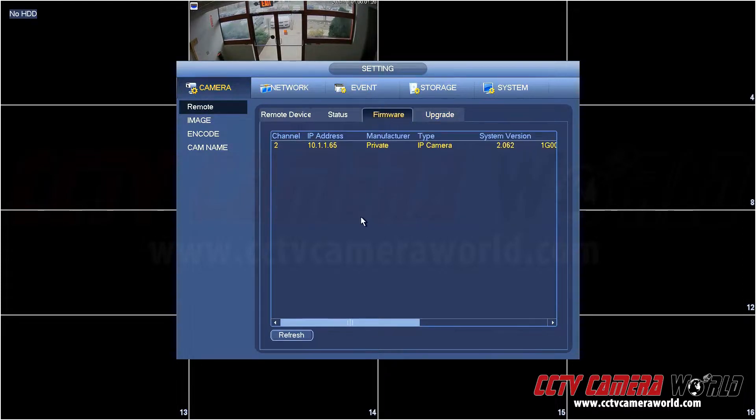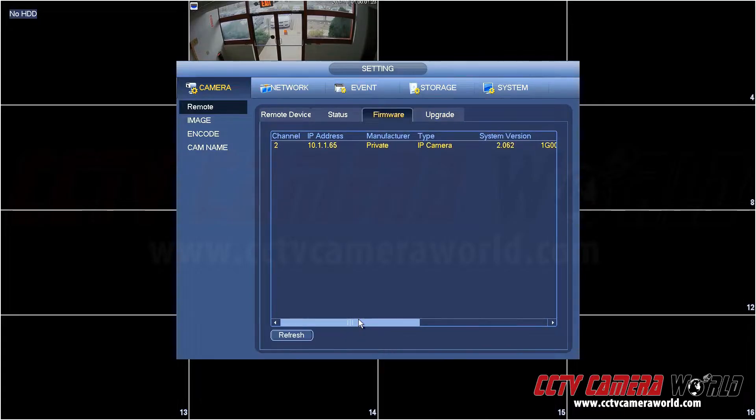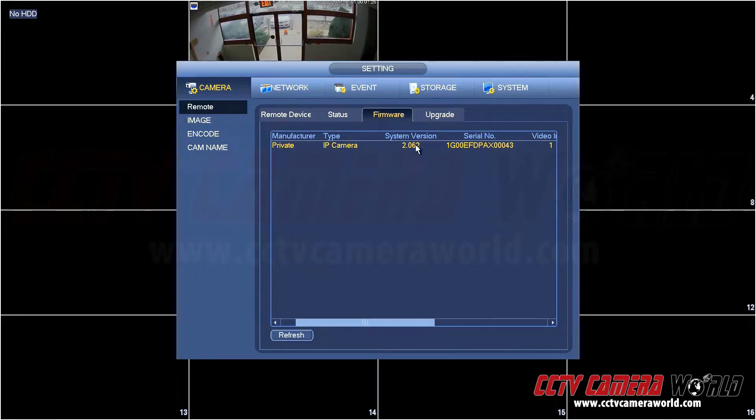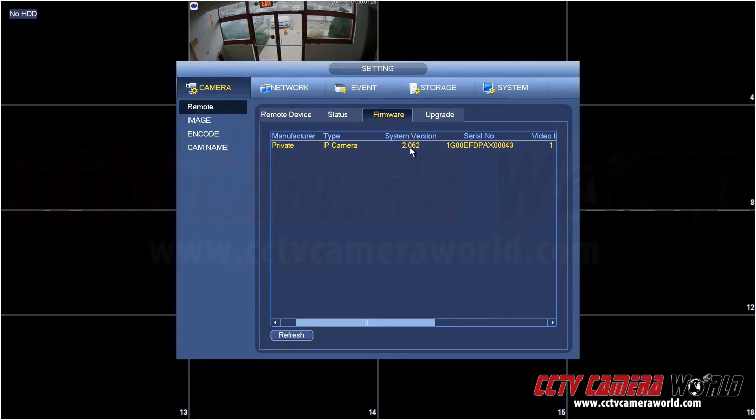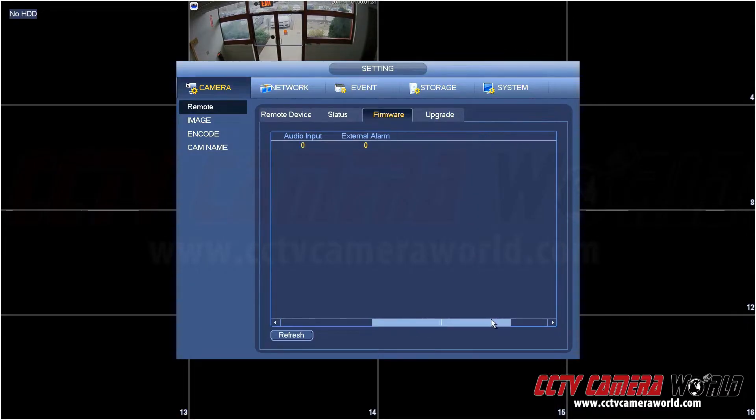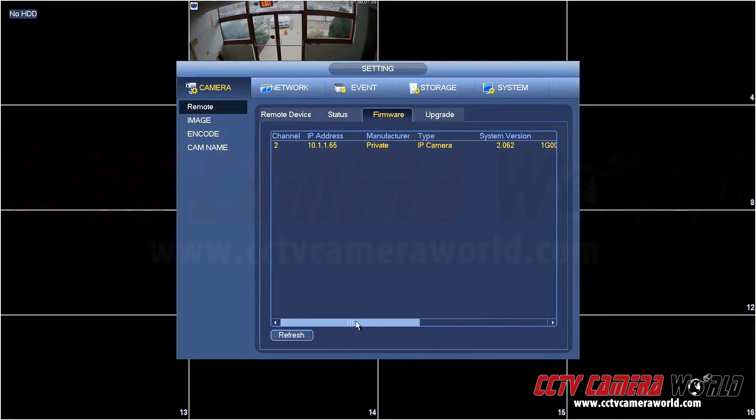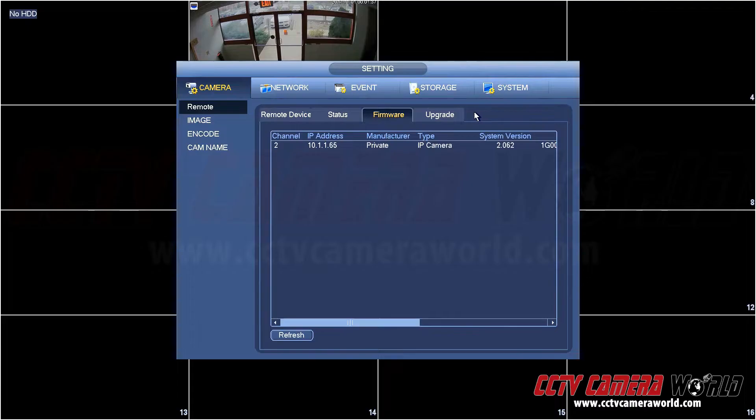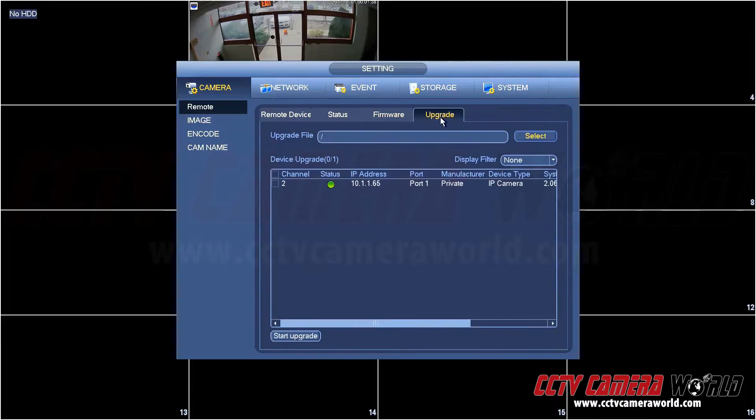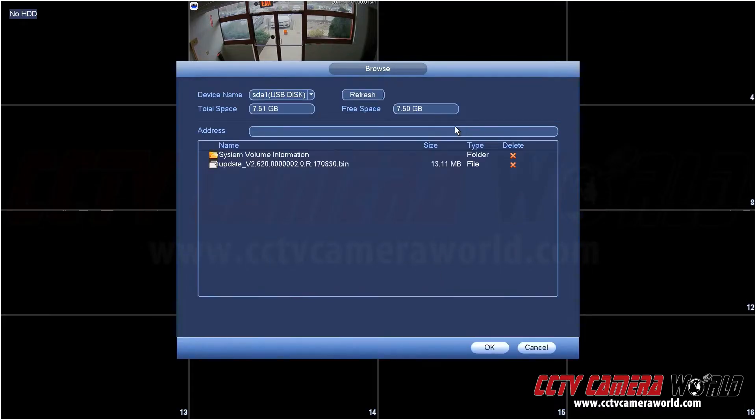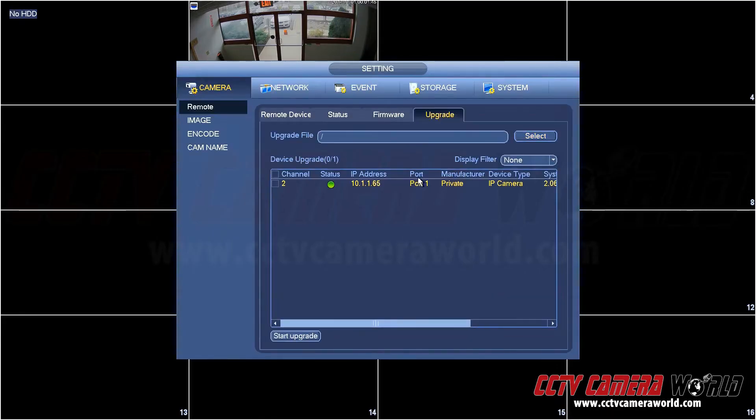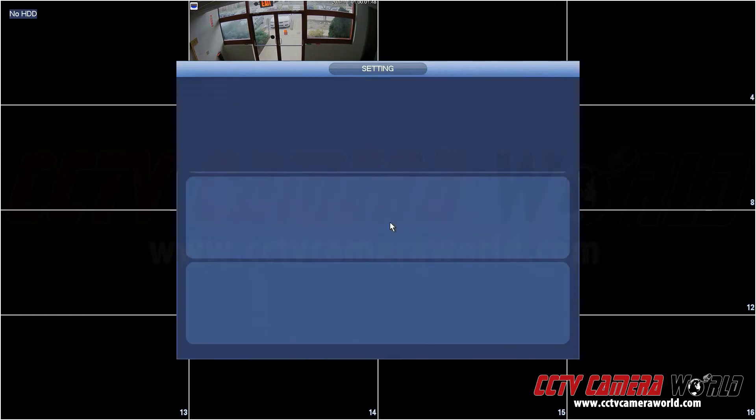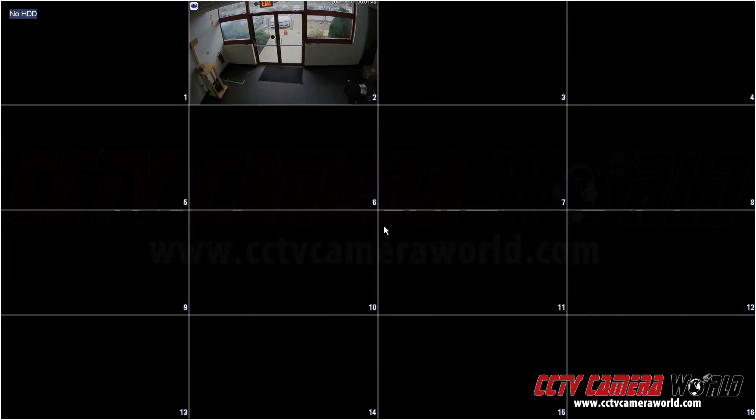Now let's go see the status of the current firmware on this camera. We see that it's changed to 2.062 which is a different version than before and it's been updated. So we've successfully applied our upgrade file. Let's go back and look at the file version. It was 620 and that's what it says, 620, so we're all good.